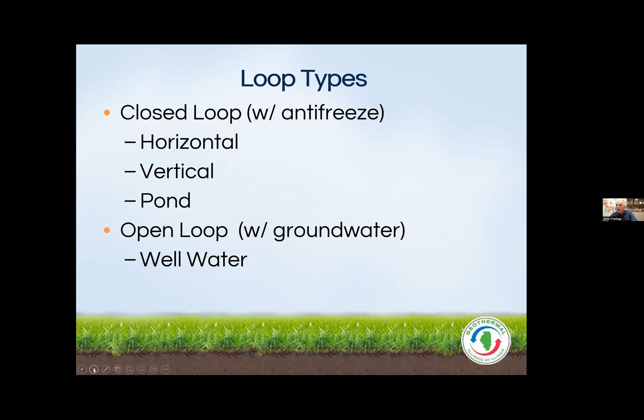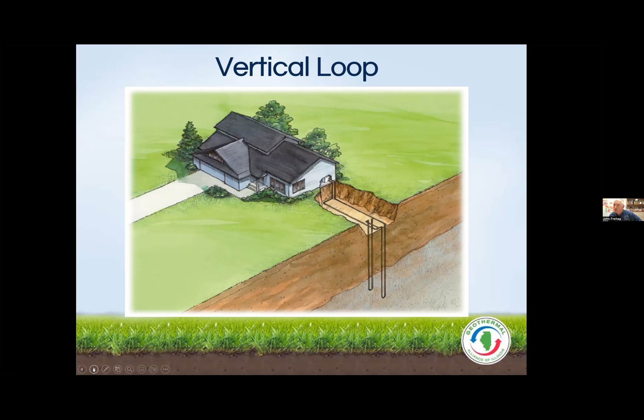This is what a vertical loop field looks like. Again, this is what's in my front yard - I have three 175-footers. These loops can be as deep as 800 feet - there are some 800-footers in the Chicagoland region, and commercial systems up to 500 feet deep are fairly common. Typically in a residential system, 150 to 200 feet is very common, and most drill rigs used for residential systems are set up for 200 footers. So that's the vertical loop field.